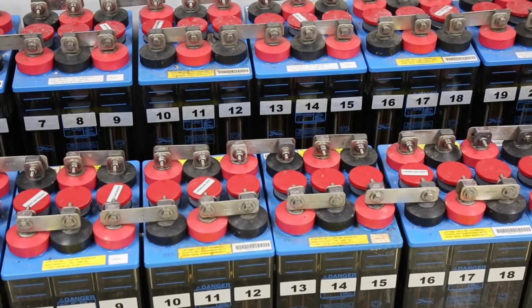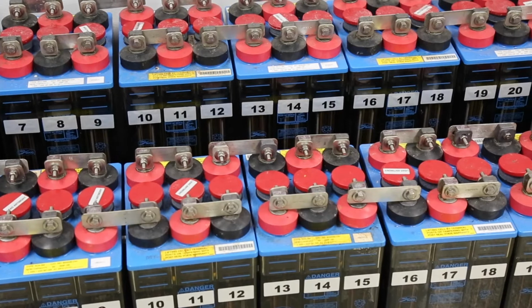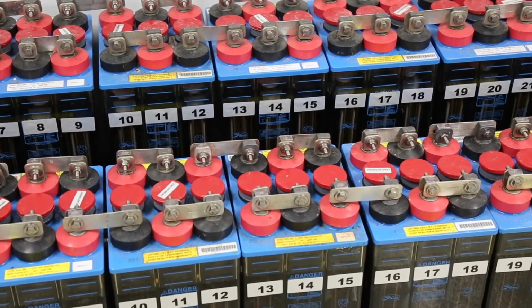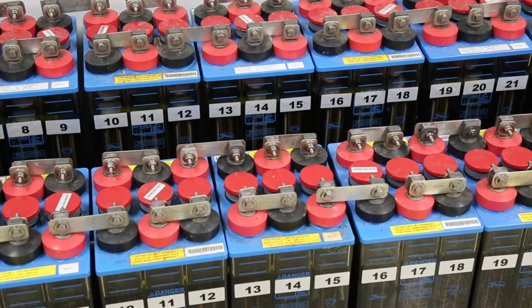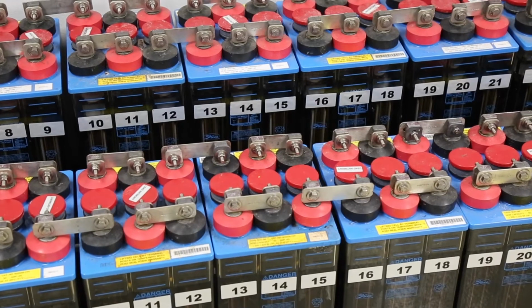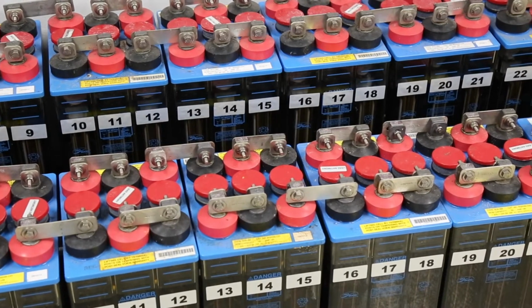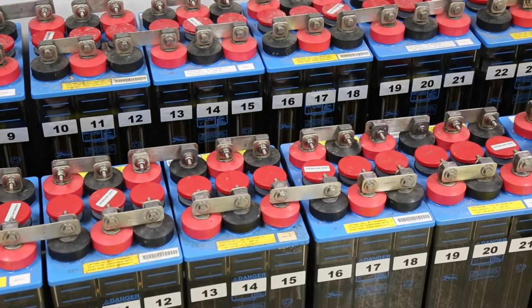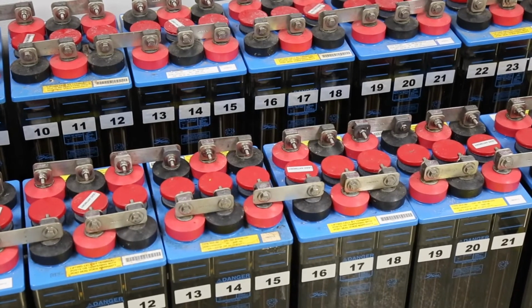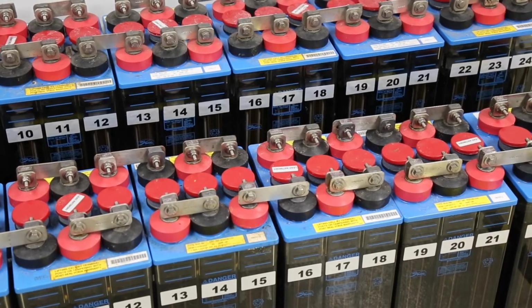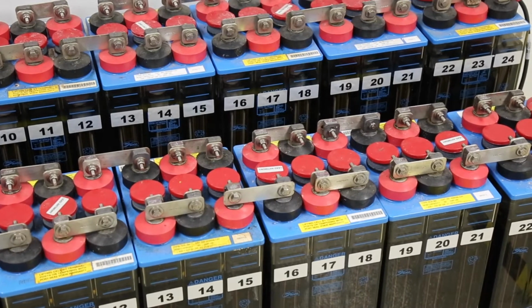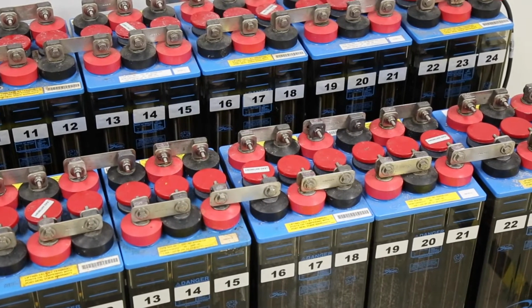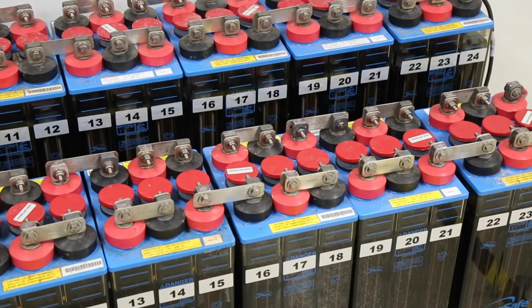You use a low resistance ohm meter because it has a higher resolution. The reason it has a higher resolution is because it tests with higher current. The same is true when testing large batteries. If you test them with a small meter that tests with limited current, you'll not have the resolution you need to see the chemical changes within the battery. This means the batteries may not work when you need them to.